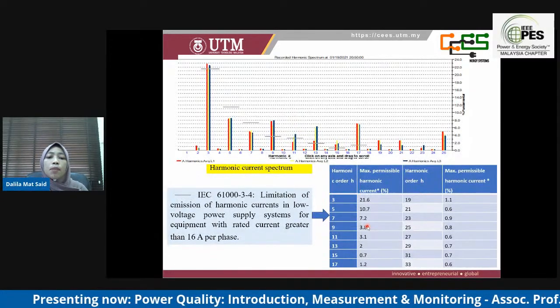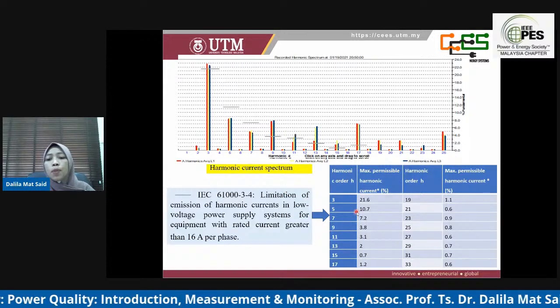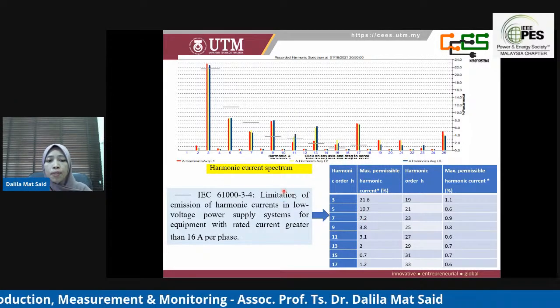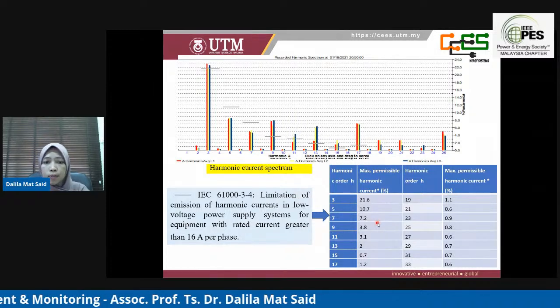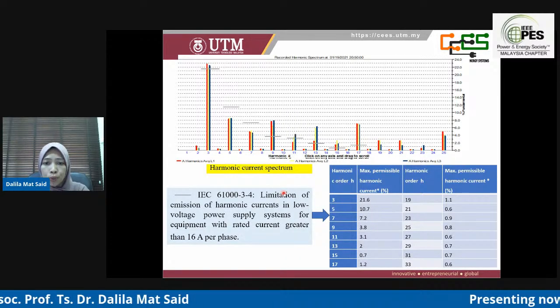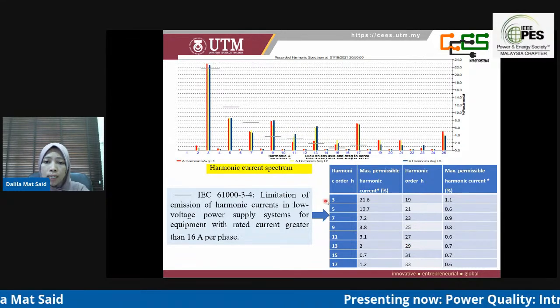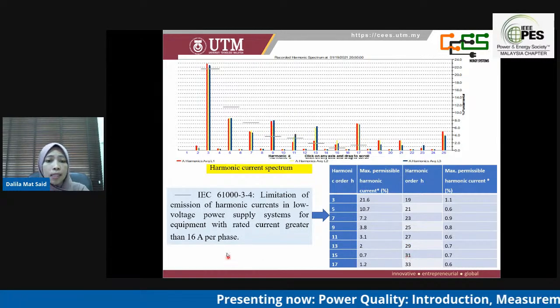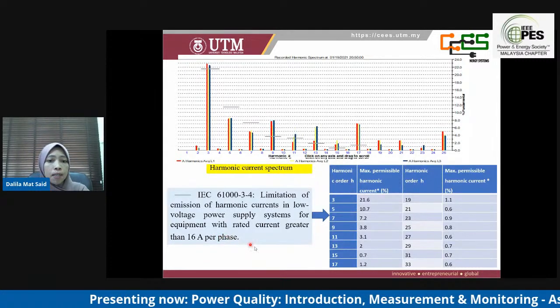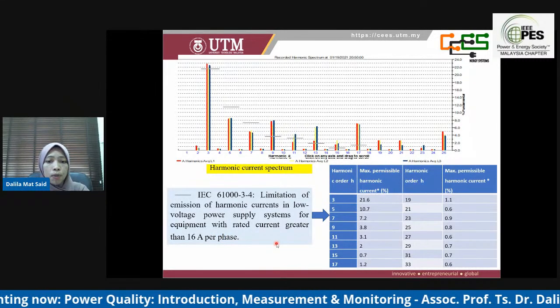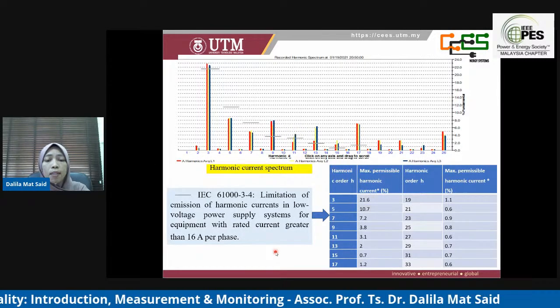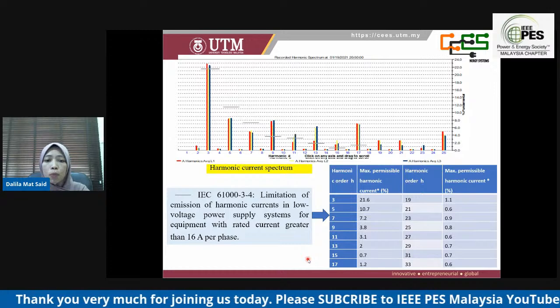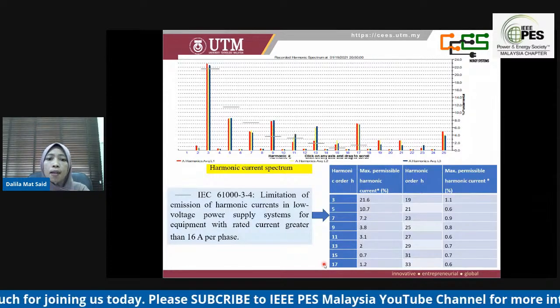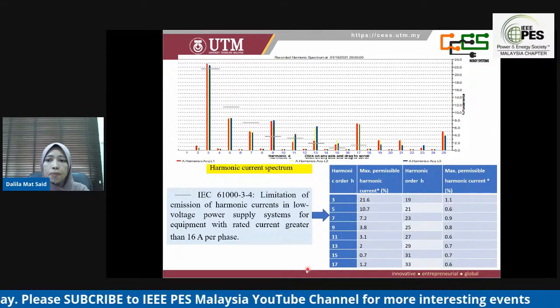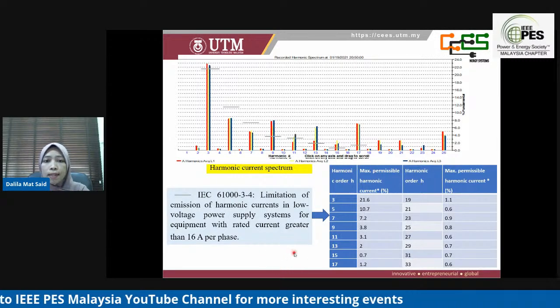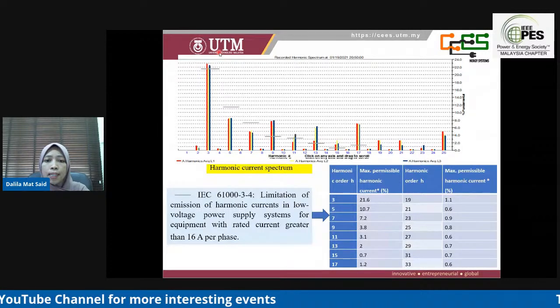By considering the harmonic data for the three-phase system, we will analyze the impact of the individual harmonics on the increase of loss for the transformer. But before that, I just want to show how we check this harmonic data against the limit. Let's say we take the limit standard, for example, IEC 61000-3-4. This is the limit of emission of harmonic current in low voltage power supply for equipment with rated current greater than 16 amps per phase. From this data, you can see the gray color that I plotted here indicates the limit.